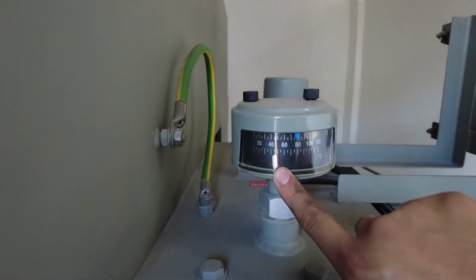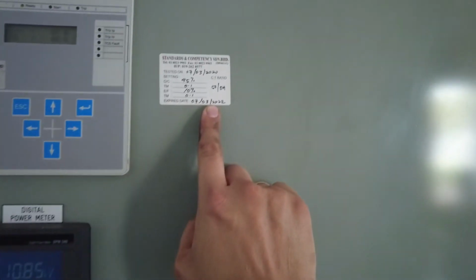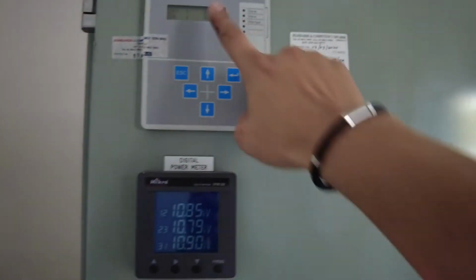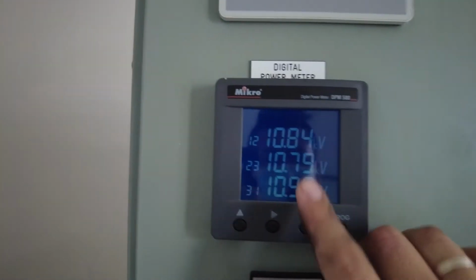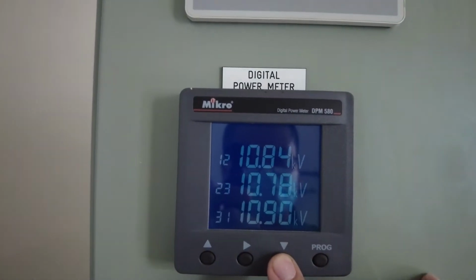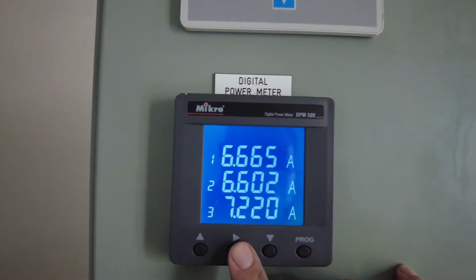Okay, now we go to the HV room. Okay, here we have the HV room, first aid chart. Let's look at the transformer temperature. Temperature is about below 50. Oil level okay. Okay, but here the VCB panel rubber mat is missing. Okay, all the tools are in place. Need to replace the rubber mat. Okay, calibration not expired. Next year only expired. Current consumption is 7 amp. Let's check the voltage. 10.8 kV currently. Amp is about 6.6 amp.